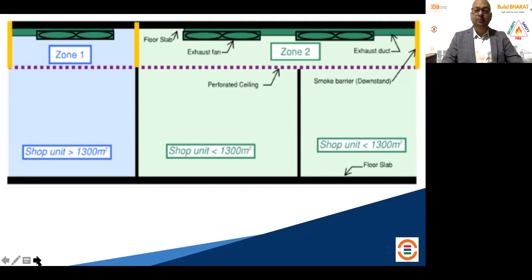So the whole point I wanted to highlight is that there are engineered ways and means to manage your smoke. But if you don't focus on smoke, because you have never experienced smoke before, and you just focus on your firefighting equipment and systems, then that's a missing area. The basement area specifically is a very, very vulnerable area where you need to manage the smoke. You need to monitor it, you need to control it. The lift well, the shaft, the staircase, the ceiling void, these are again pockets where you need to see carefully how the smoke is going to travel and from where, horizontally and vertically.